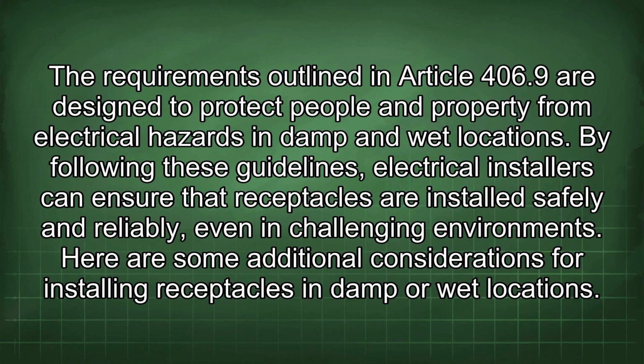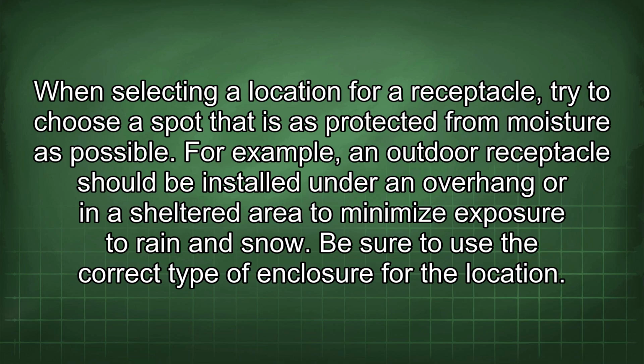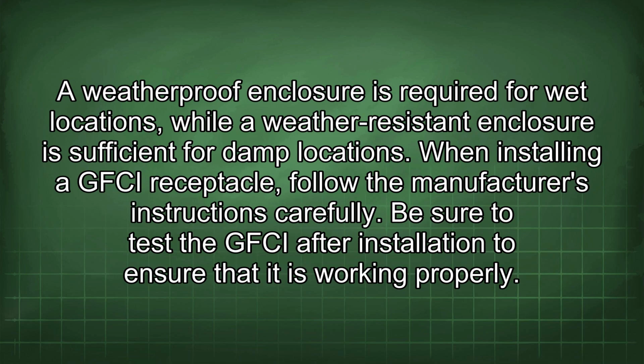Here are some additional considerations for installing receptacles in damp or wet locations. When selecting a location for a receptacle, try to choose a spot that is as protected from moisture as possible. For example, an outdoor receptacle should be installed under an overhang or in a sheltered area to minimize exposure to rain and snow. Be sure to use the correct type of enclosure for the location. A weatherproof enclosure is required for wet locations, while a weather-resistant enclosure is sufficient for damp locations.